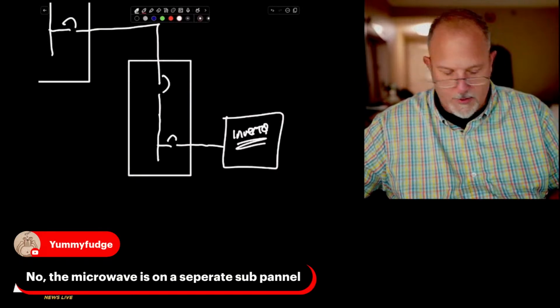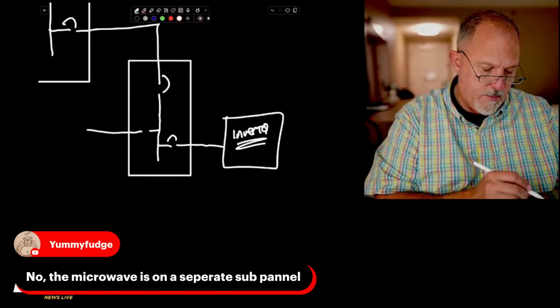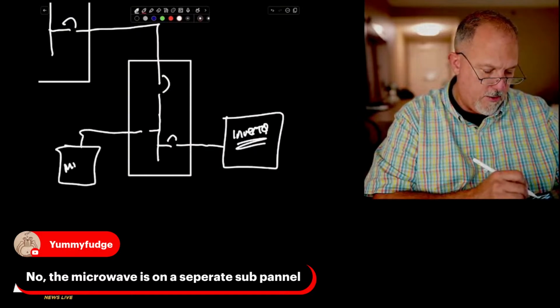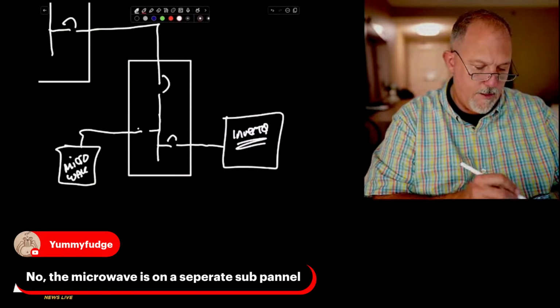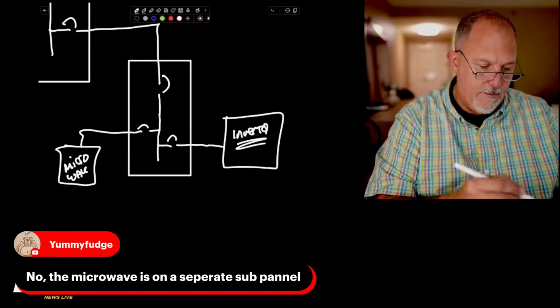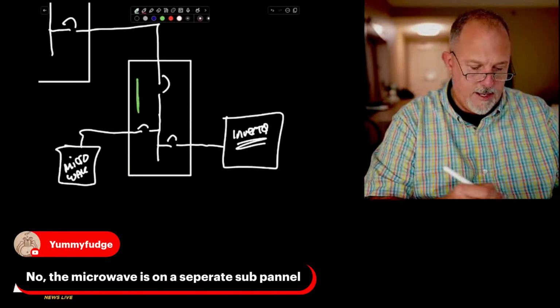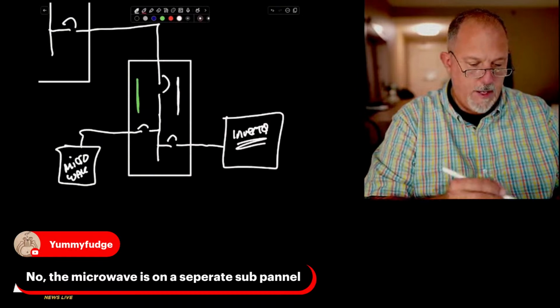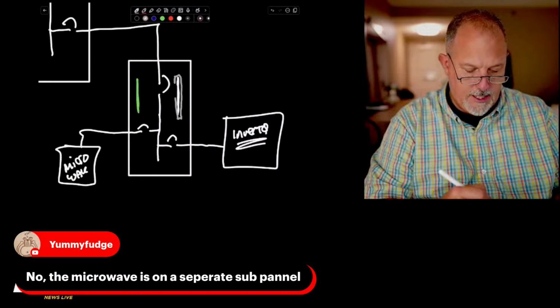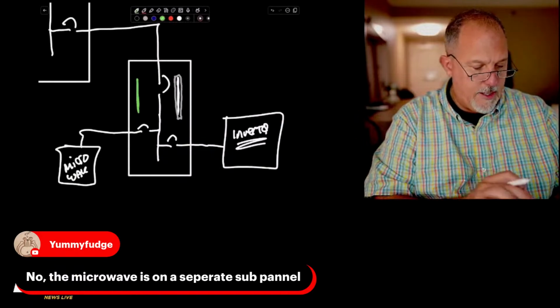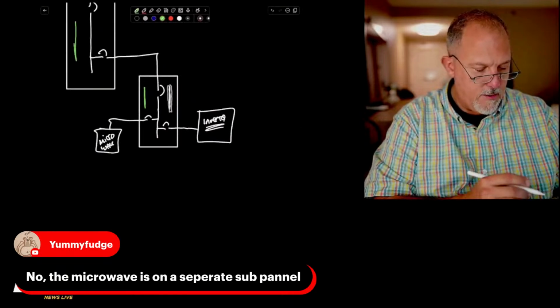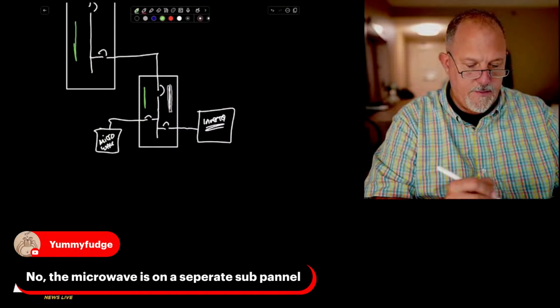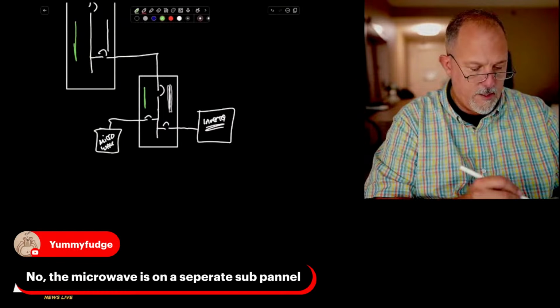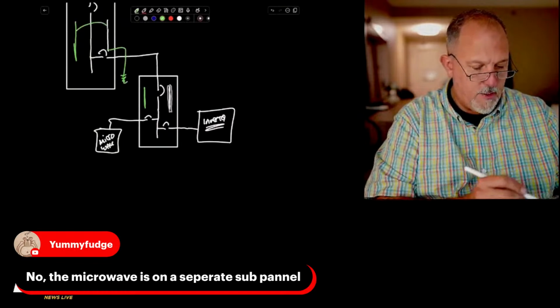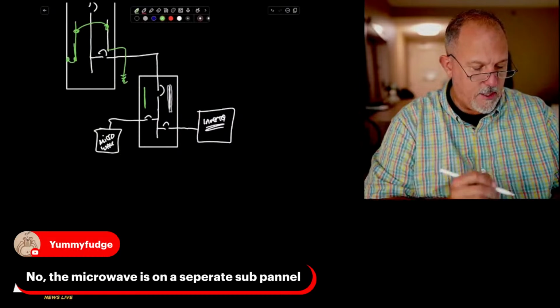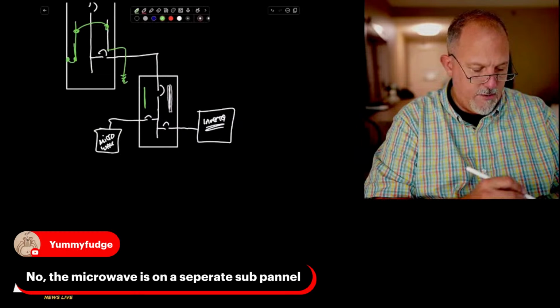No, the microwave is on a separate panel. So, all right, let's do this. This is my microwave. Right? Now, I have a ground bar here, and I have a neutral bar here, and the neutral bar is insulated. I would be over here for my ground bar, and let's say I have a neutral bar here. Come off of that, I go to ground. I bond those two together. I bond that to the enclosure, and my microwave, I come back with a ground.